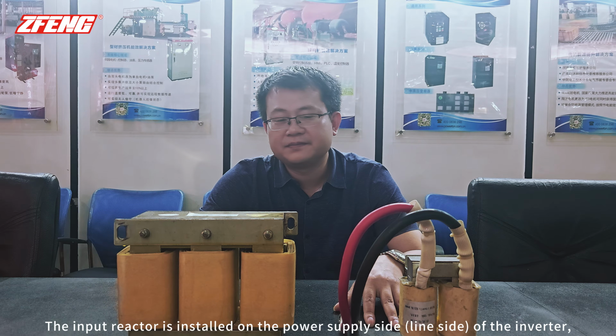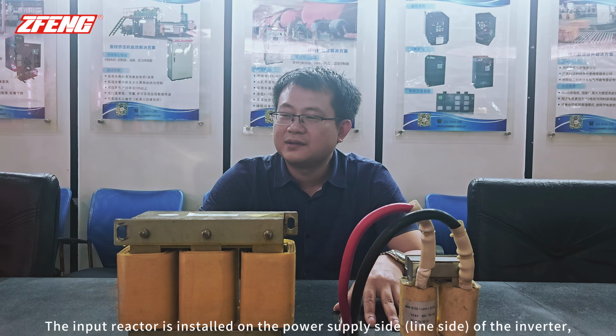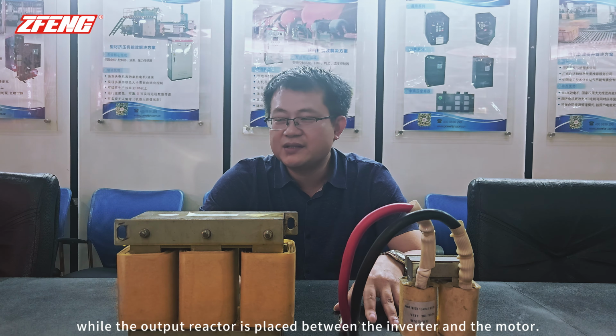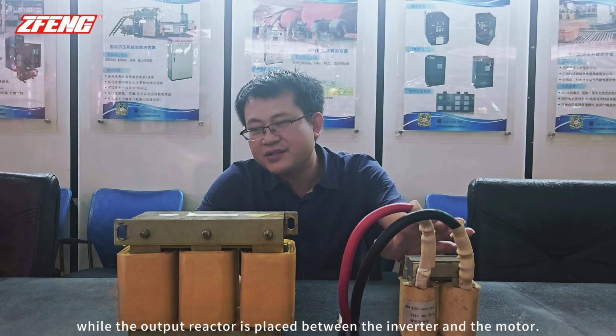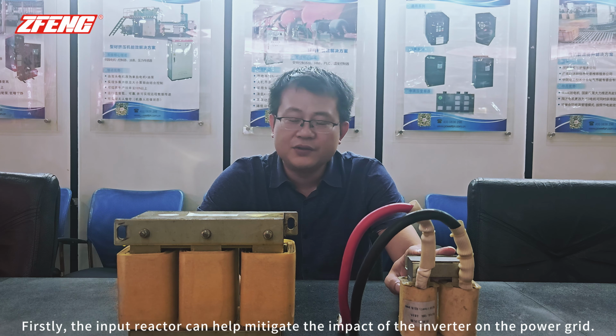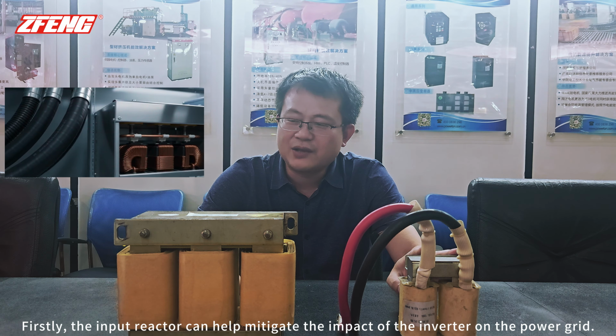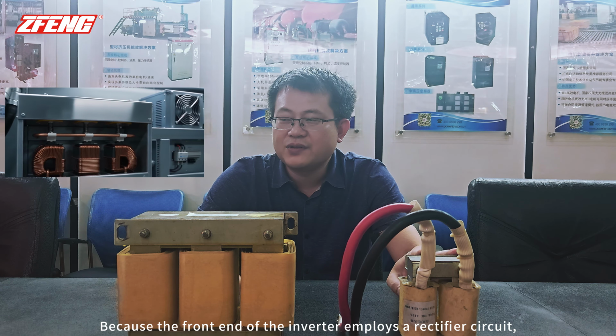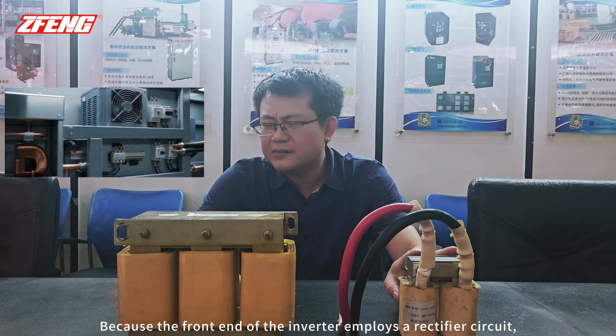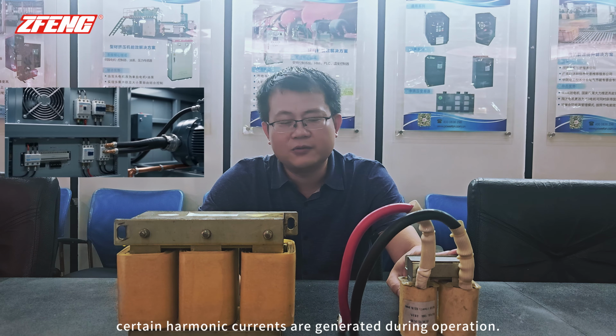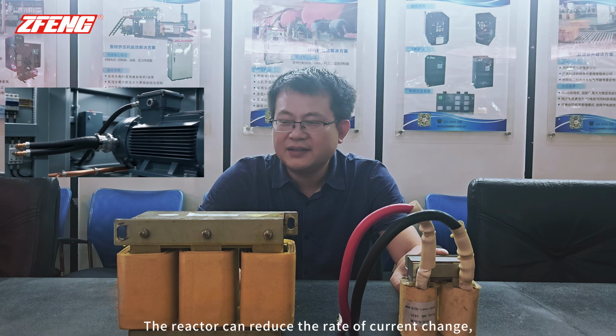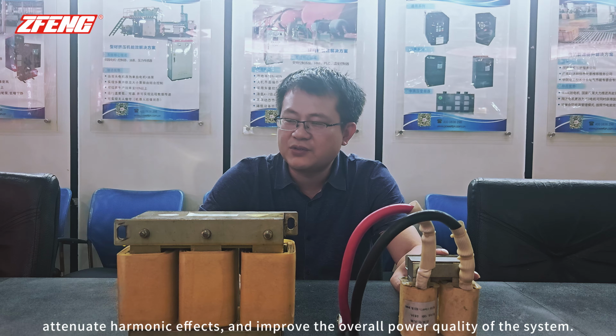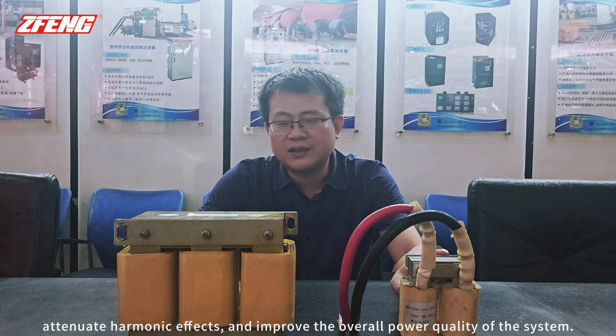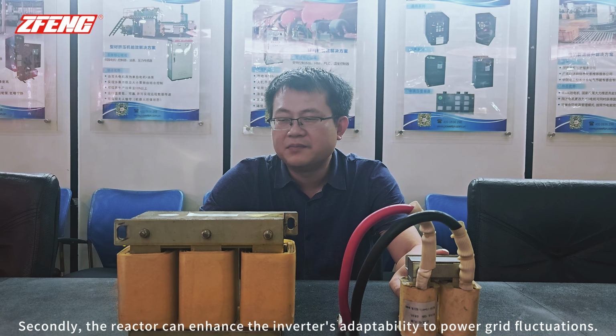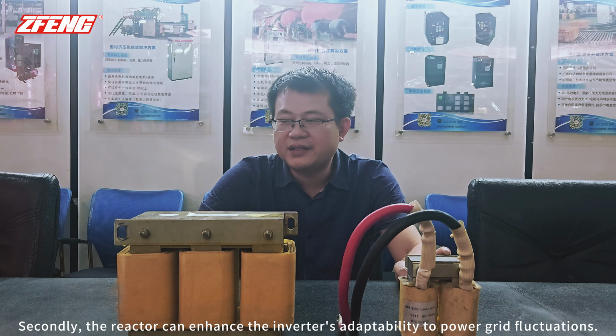The input reactor is installed on the power supply side, the line side of the inverter, while the output reactor is placed between the inverter and the motor. Firstly, the input reactor can help mitigate the impact of the inverter on the power grid. Because the front-end rectifier circuit of the inverter generates harmonic currents during operation, the reactor can reduce the rate of current change, attenuate harmonic effects, and improve the overall power quality of the system. Secondly, the reactor can enhance the inverter's adaptability to power grid fluctuations.